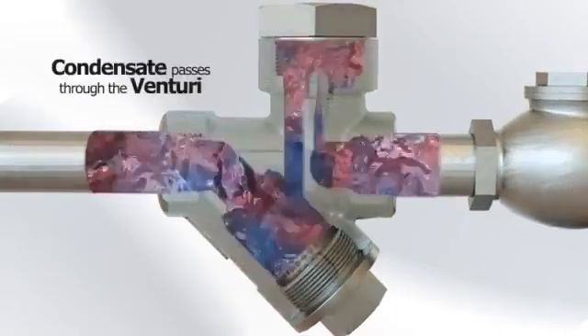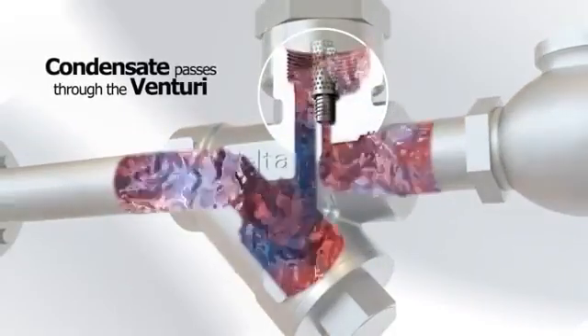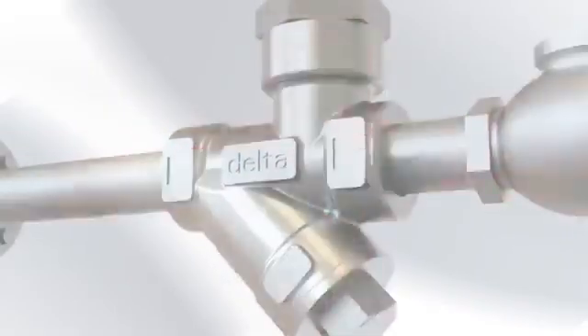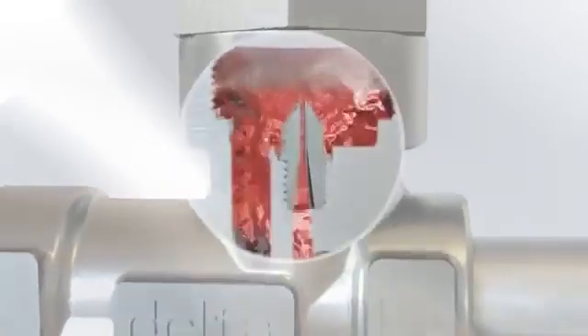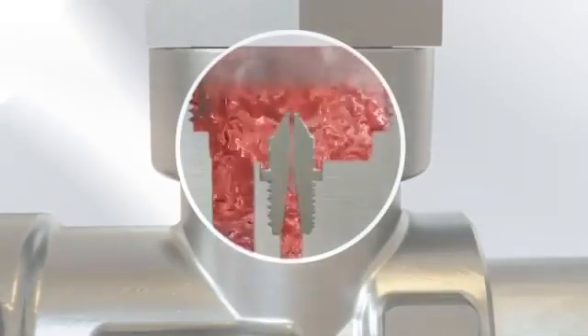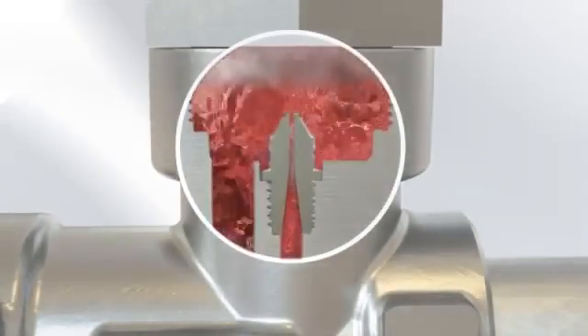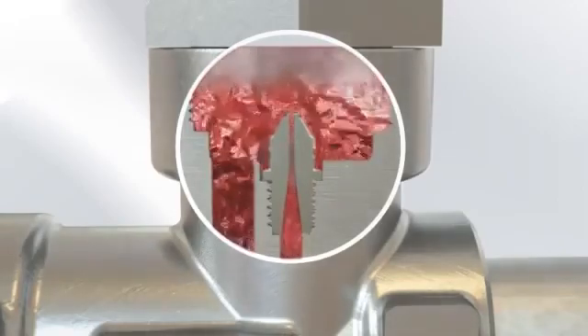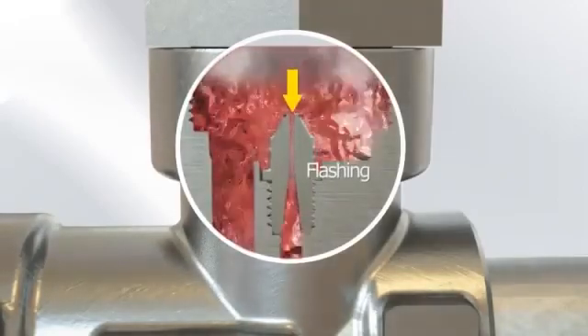This hot condensate passes through the orifice and enters the mouth of the Venturi. As the condensate passes through the mouth of the Venturi, there is a sudden pressure drop, which causes a percentage of the hot condensate to change phase from condensate to steam, a phenomenon known as flashing.